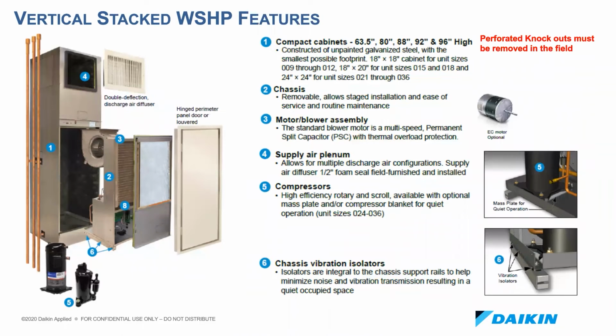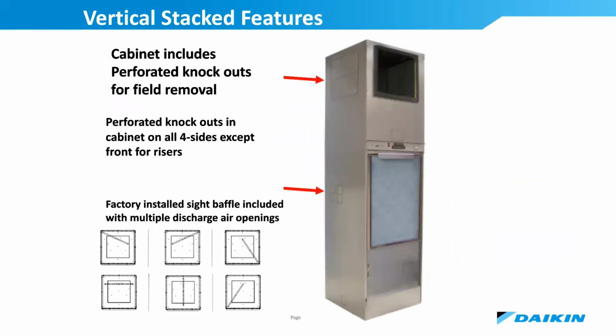The chassis and the cabinet are separate components. Typically, it's a staged installation, so the cabinets and the risers are installed first, followed by the chassis and the hoses, then the return air panels and discharge grills. The cabinets are available in sizes 63.5 inch, 80 inch, 88 inch, 92, and 96 inch high. The perforated knockouts must be removed in the field for the discharge air and the riser locations.